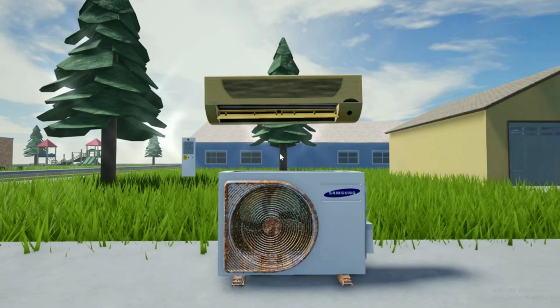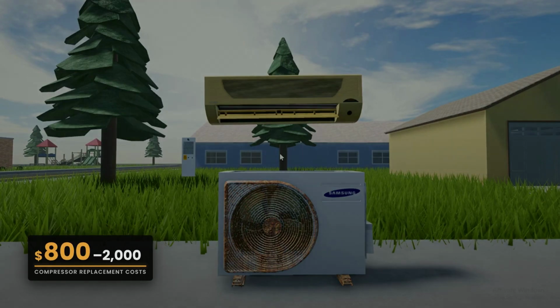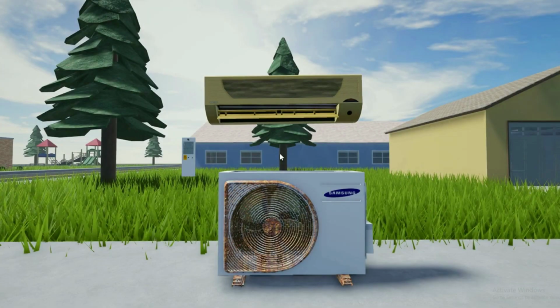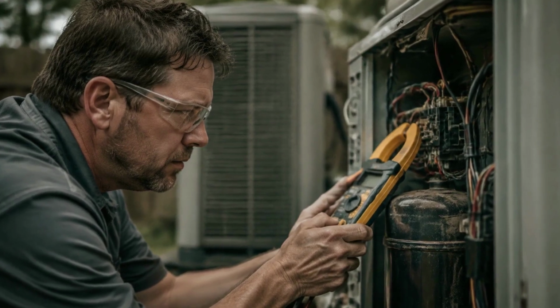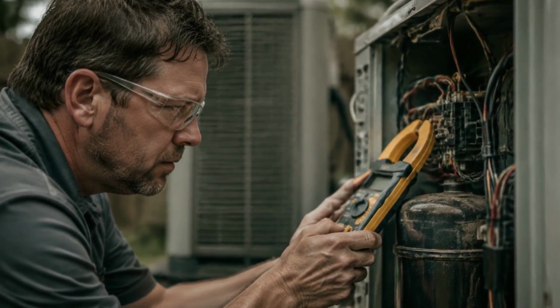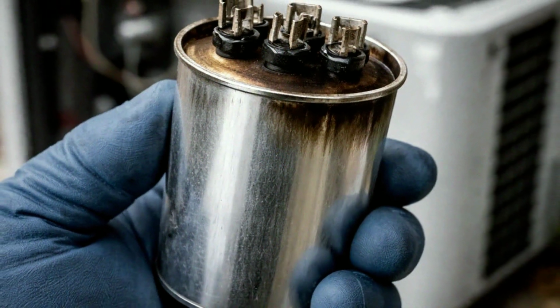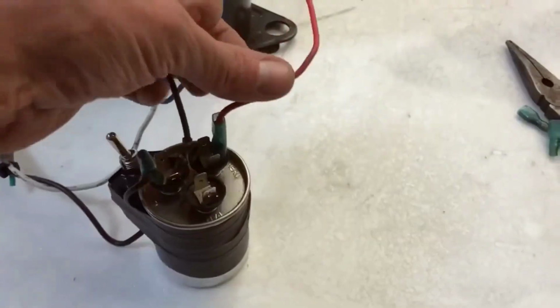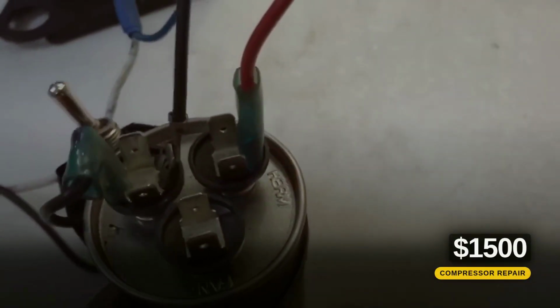The compressor is the most expensive component in your AC system. Replacement costs run between $800 and $2,000 for the part alone, not counting labor. A weak capacitor that forces the compressor to hard start repeatedly, drawing 2 to 3 times its normal startup current, accelerates wear on that compressor. The capacitor failure and the eventual compressor failure are not independent events. One leads to the other. A $30 repair ignored long enough becomes a $1,500 repair.